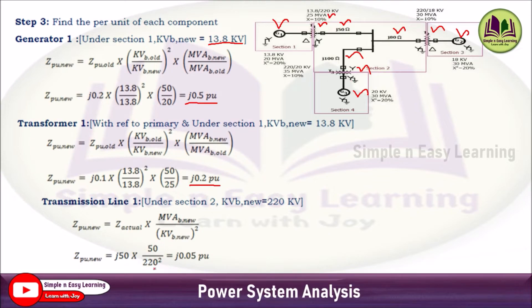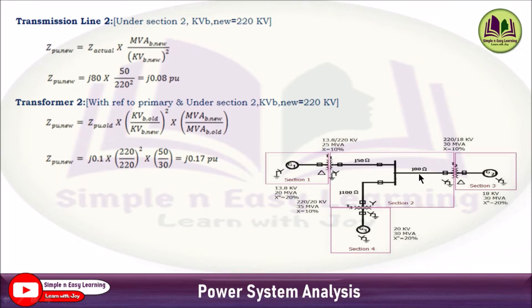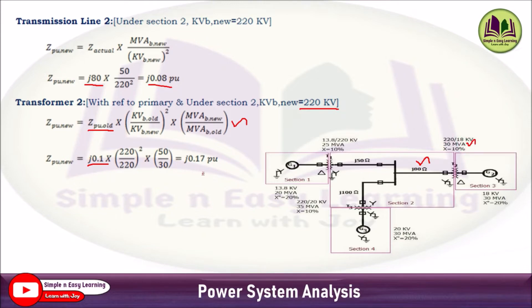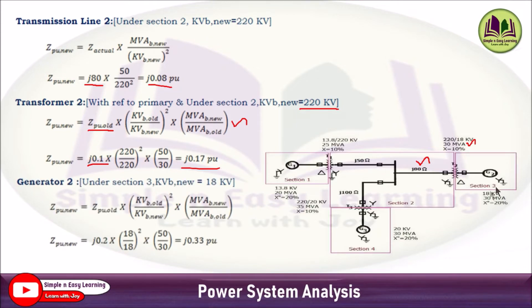For transmission line 2 (j80 ohm, section 2): j80 × 50/220² = j0.08 per unit. For transformer T2 (primary under section 2, rated 30 MVA, 220/18 kV): Z_pu_new = j0.1 × (220/220)² × (50/30) = j0.17 per unit. For generator G2 (section 3, base kV = 18 kV, 20% reactance): j0.2 × (18/18)² × (50/30) = j0.33 per unit.